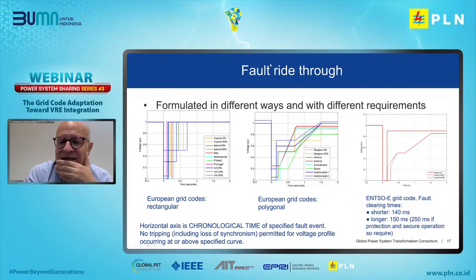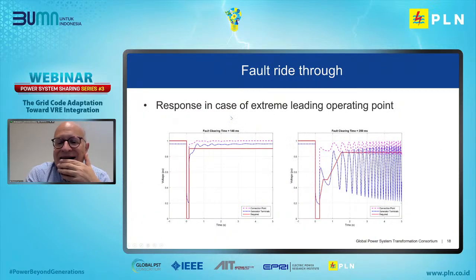Even so, can you please go to the next slide? We found that in some conditions not defined in the grid code, precisely the extreme leading operating point, the more demanding requirements meant synchronous machines would not be able to fulfill them. So here there is a lesson: before imposing a requirement, you must check if standard equipment would be able to fulfill it. It does not make any sense to impose a requirement that is not possible to fulfill.